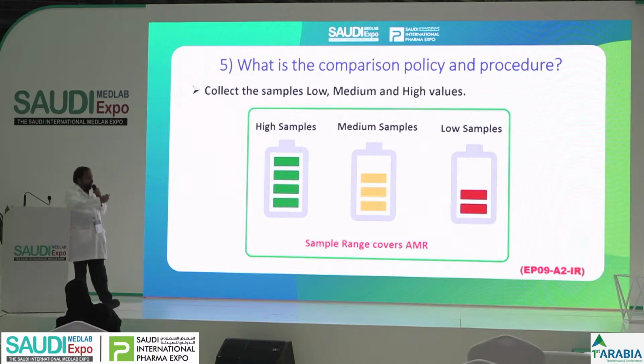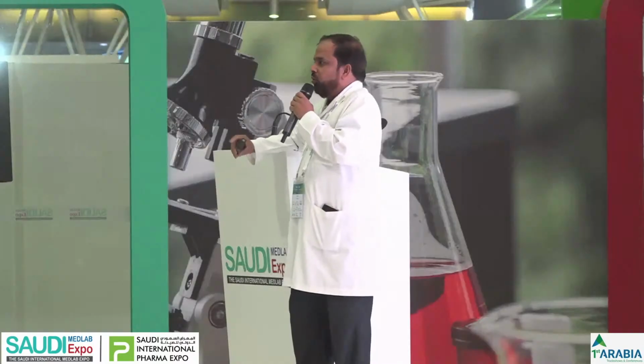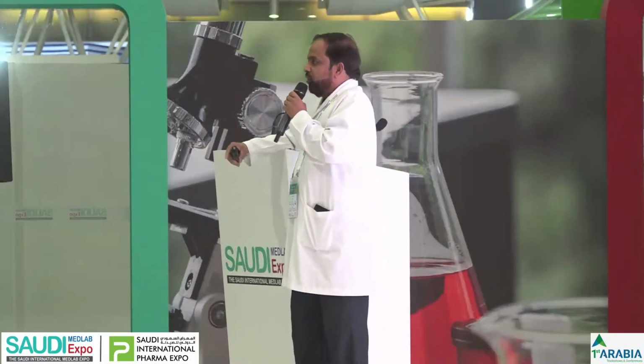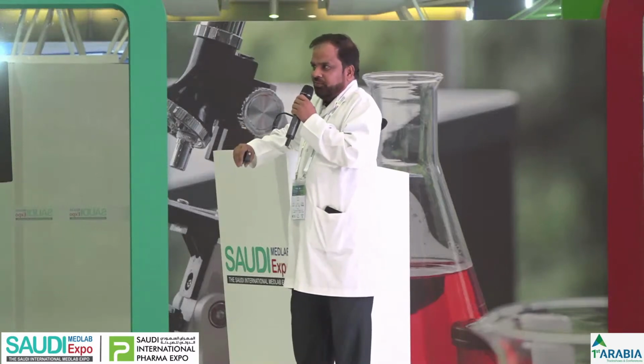And when I ask, okay, why don't we have a low sample? Or why don't you have a high sample? Or three ranges of sample? They say, we don't have a sample. There is a way to make the sample. You spike the QC, you spike the calibration. You have a normal sample, you spike the high sample. But there is no way to escape. You have to do it. If not, it's not going to pass.